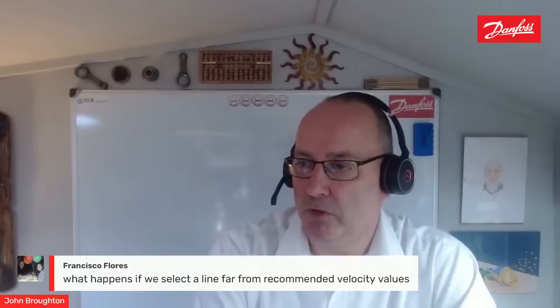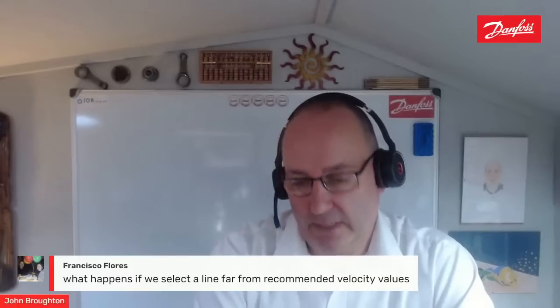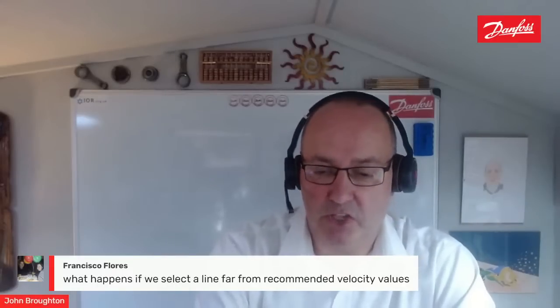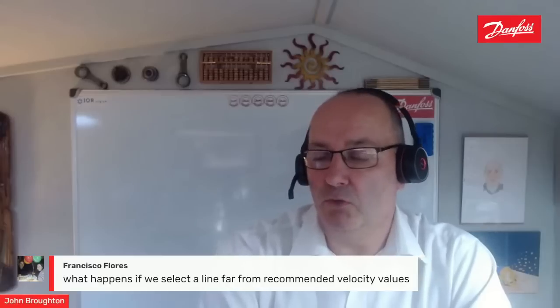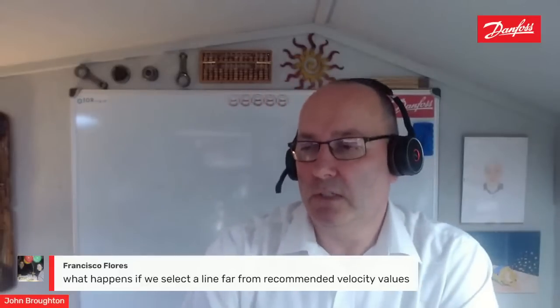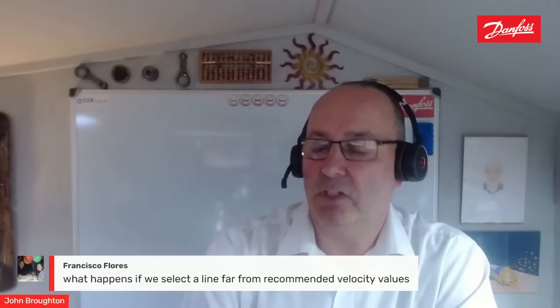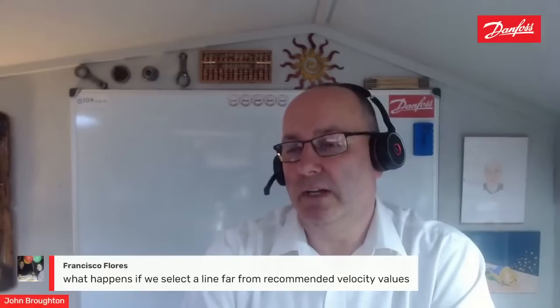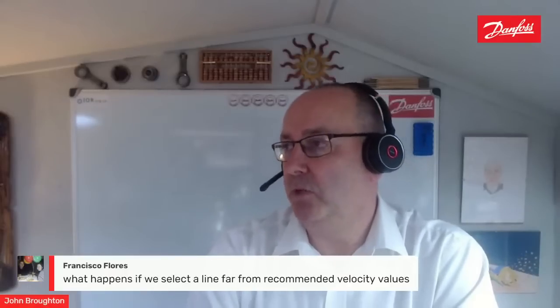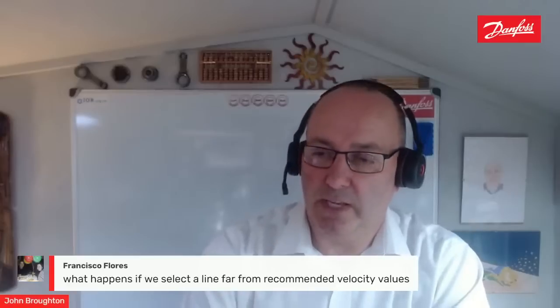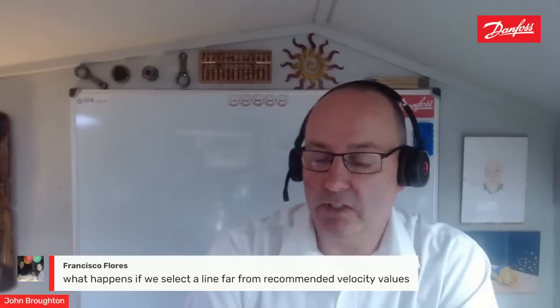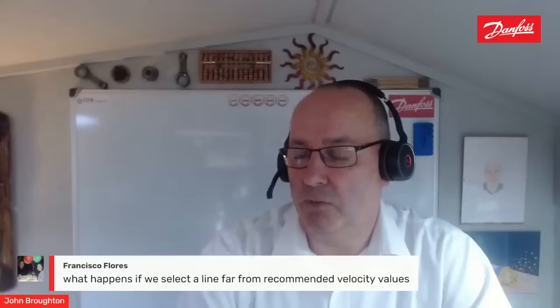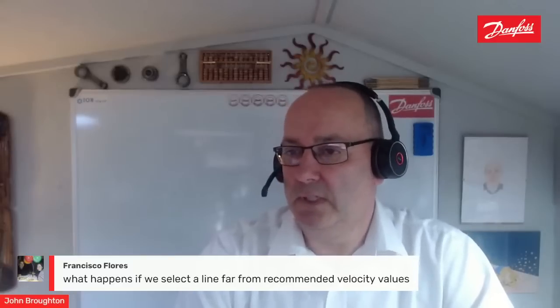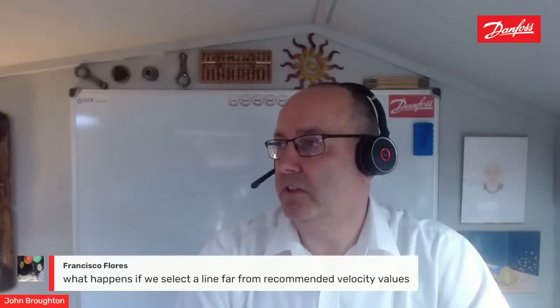From a suction line point of view, again, coming back to what I say, if we get the wrong velocity, too low velocity, we won't get oil back to the machine. If we have too high velocity, we'll have a suction penalty, and the compressor will need to be slightly larger than it needs to be because of that suction line pressure drop. So hope that answers that question, Francisco.